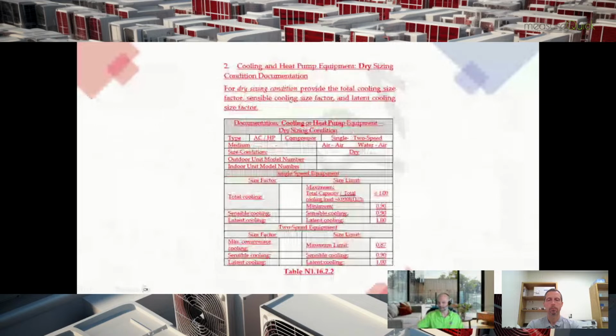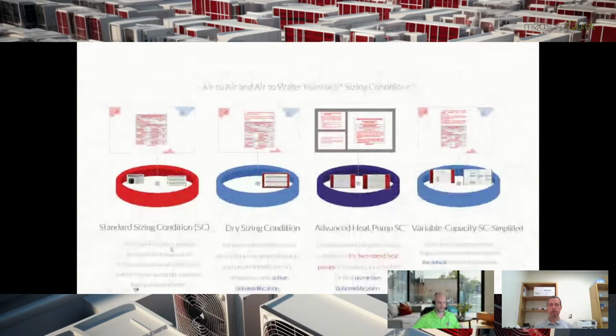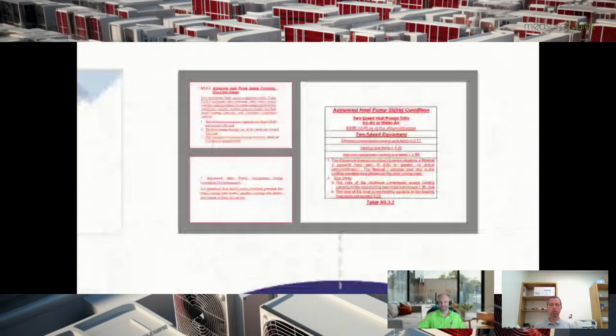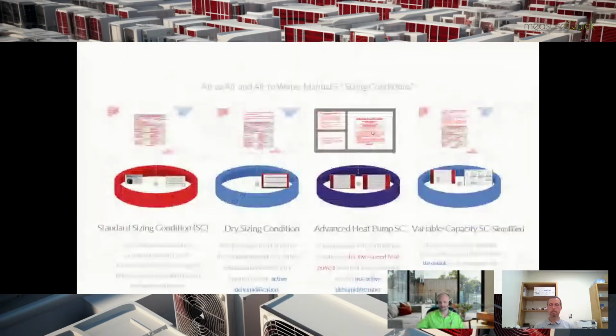Dry sizing condition is basically either you're in a climate where there's no latent load at all, a sensible heat ratio of 95% or better, 0.95 or better, or you're using a dehumidifier. And then there are some really cool things that you can do if you're using a dehumidifier that will allow you to size HVAC equipment, either heat pumps or air conditioners, a lot bigger than what we normally would. And it allows us to do some things like pay attention to the heating load and try to find a balance point. And Anthony's going to talk about all these during his portion of the presentation here.